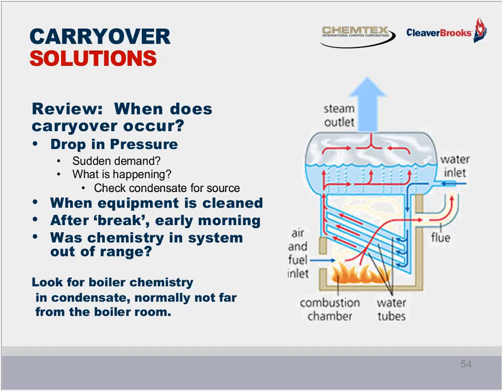The lesson to be learned here is take a look at the boiler chemistry, not just in the boiler, but look at the chemistry in the condensate as well. If you've got a little carryover in the boiler water, it's going to show up in the condensate, but typically not too far from the boiler unless you have a real problem.